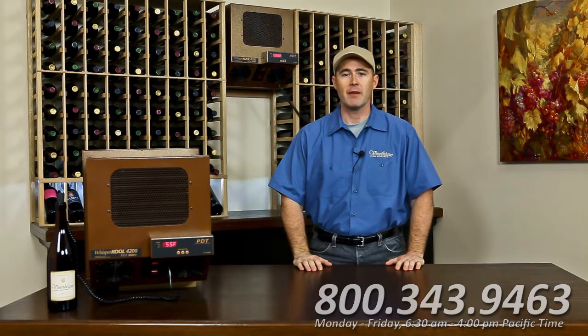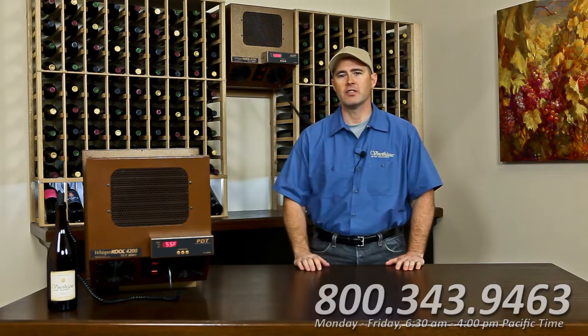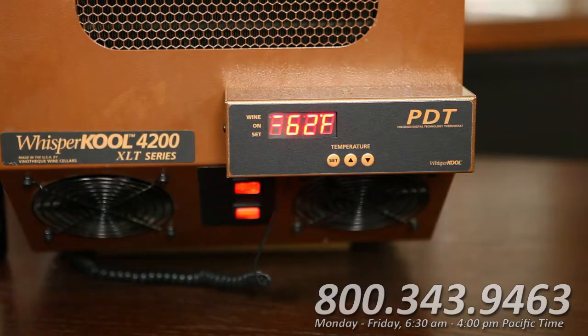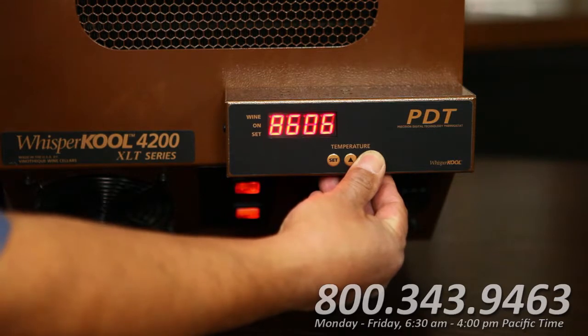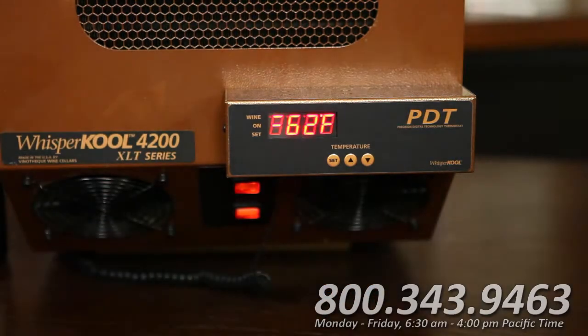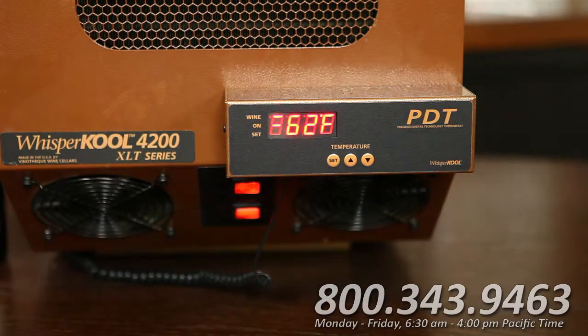Next, you should run the bypass test that we just showed. Also, there's another way to test your thermostat. Press and hold the down arrow while the unit is running. You should see a 90-minute countdown on the display because the unit will only run for a maximum of 90 minutes at a time. If there is no countdown, or if the unit does not turn off at the end of the countdown, then you have a thermostat problem.